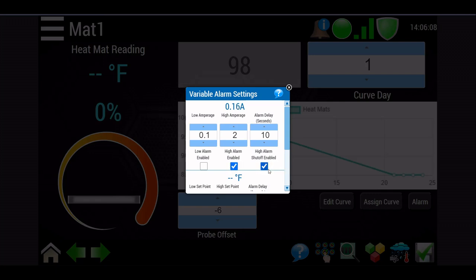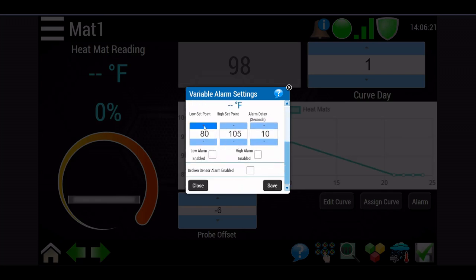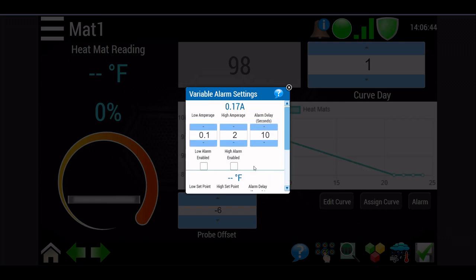And you can also see there is the option to have, if there is a high alarm, you can completely shut it off automatically or not, depending on how you want it to operate. And then as well, we have our temperature set point alarms if it gets too warm or too cold. Same thing, you also have an alarm delay for these two, and you can enable them or disable them. And then as well a broken sensor alarm if you want it to be detecting if that temperature sensor has broken. So that is the alarms settings.